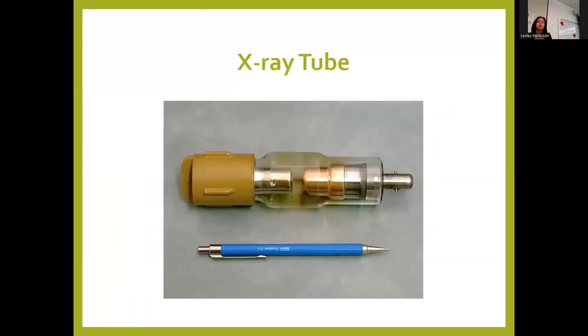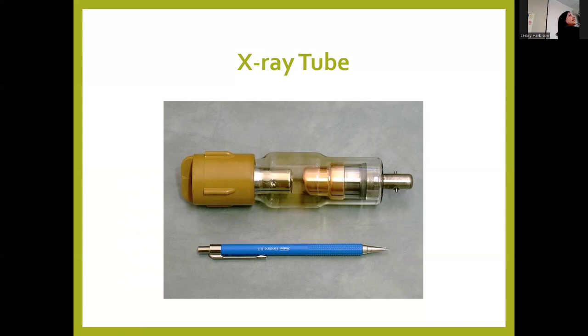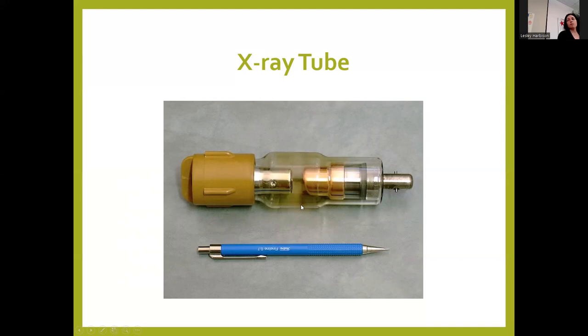We're going to review the X-ray tube — the vacuum-sealed tube inside the tube head. The big thing you actually move around with the BID coming out of it is your tube head, and inside is the X-ray tube with the cathode and the anode. You can see it's small — the size of a pencil or pen — with a brownish color, which is the leaded glass. There's a tiny window in there that lets the X-ray photons come out after the reaction has occurred.